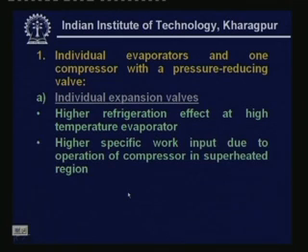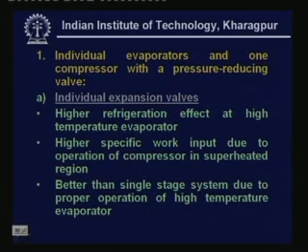To summarize: this system uses two evaporators, a single compressor, and individual expansion valves. It gives a higher refrigeration effect at the high-temperature evaporator, but also higher specific work input due to operation in the superheated region. COP may not increase greatly, but the system is preferred for proper operation of the high-temperature evaporator.